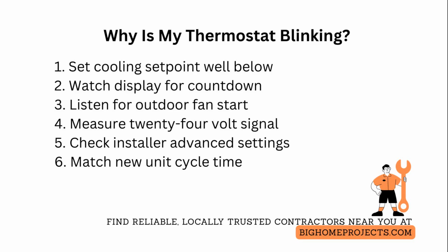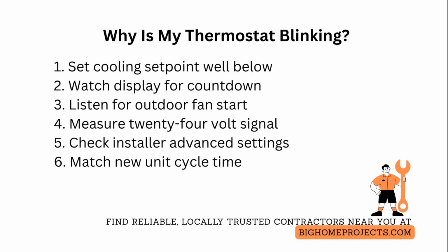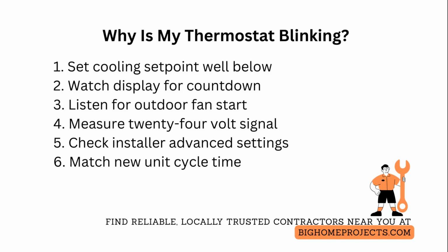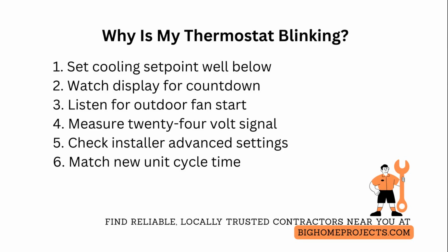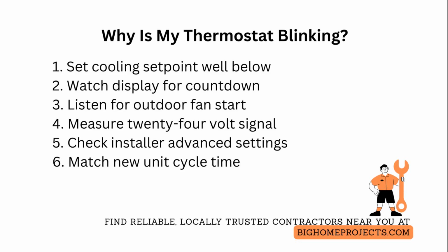If you want to verify behavior without tools, set the cooling set point well below room temperature. Watch the thermostat display for the countdown or blinking indicator and listen at the outdoor unit. You should hear the fan start before the compressor, and the compressor will not energize until the delay completes. For a tech level check, measure the 24-volt control signal at the air handler or outdoor contactor terminals with a multimeter while the thermostat is in the waiting state. You should see no continuous 24-volt call to the contactor until the timer ends.